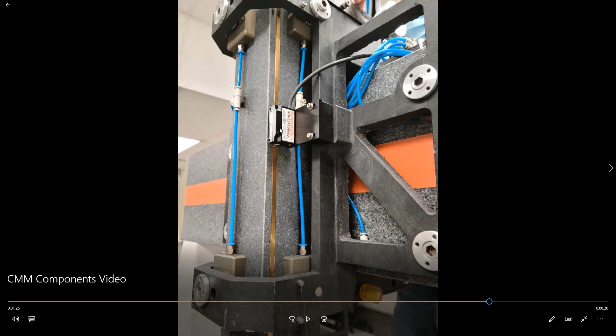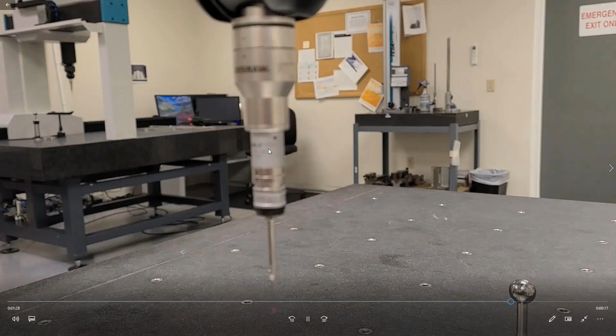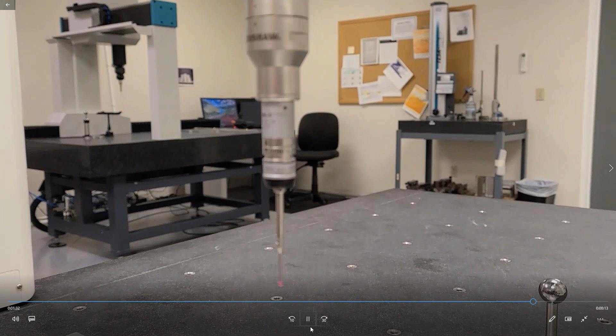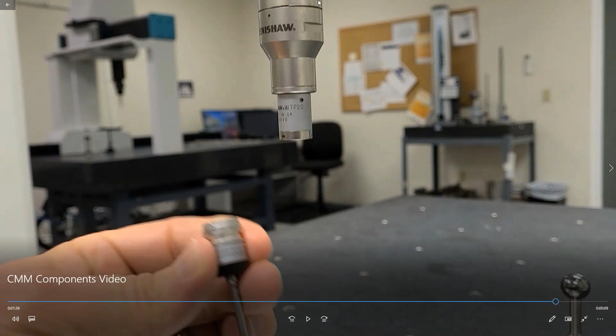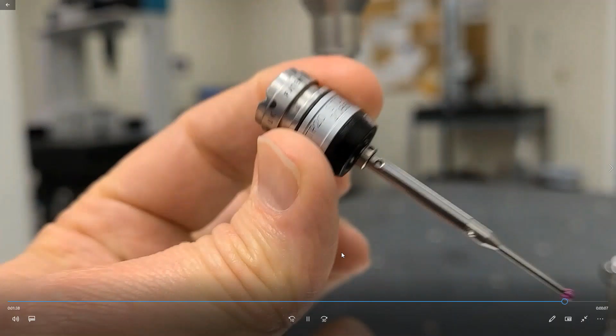And so while it was apart, I took some of these pictures. Notice the Z-axis here. Again, we have several bearings all around the axis. And then this copper-colored strip is the scale. And this is the reader that provides the feedback from the scale so that the CMM knows where it is. This is our probe. Above this was the probe head. You've got your probe module, the extension, and your actual stylus. A lot of times when people say probe, they really just mean the stylus. It's actually a combination of all these things.